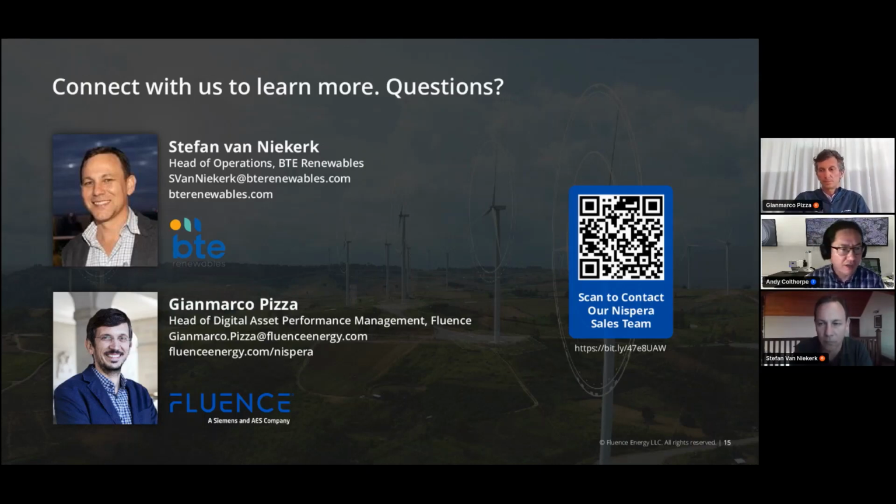Okay, and these questions are pretty heavy on the emphasis on battery storage. So I don't know if there's anything to be said in terms of warranties and performance guarantees for other types of clean energy technologies. Stefan, do you have any particular comment on that? Yeah, I think the value lies in doing comparisons. So you can find equipment that is performing not the same as the others. When you are looking at, let's say, a serial defect, it will be difficult to pick that up if it's across the board. But the value really lies in having the performance of a large number of systems, and you can accurately see when the performance is out of line with the rest. That's where we've been able to use it successfully on component level, or maybe more string level, and then on plant level. Performance on plant level is very easy. When you go down, it's a little bit more tricky to get to the warranty stage, but you can see an outlier for sure.